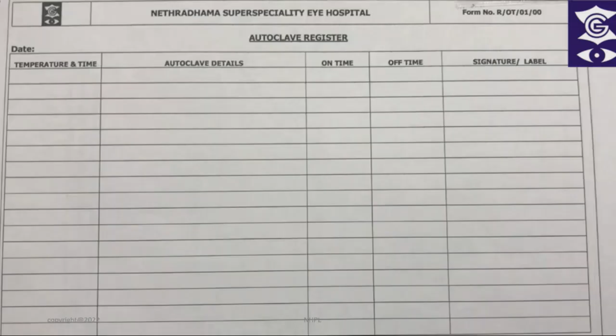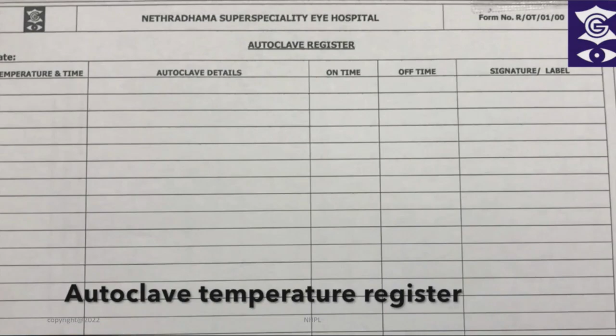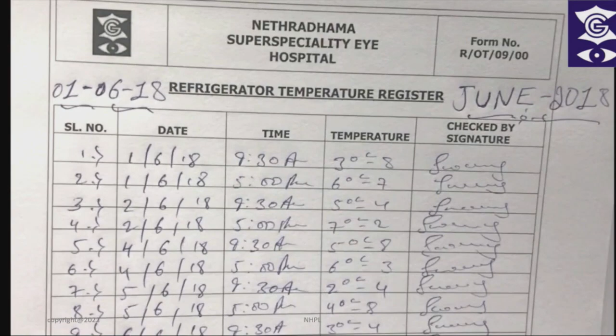Of the various registers, the autoclave register. These are some of the formats that we follow. The sterilization register, the temperature monitoring register, microbiological culture report, OT disinfection register. If you have various OTs, this is how it is monitored. Medical gas cylinder register, medical supply stock register, OT utilization, which we analyze at the end of every month. The refrigerator temperature register, checked twice a day and recorded.